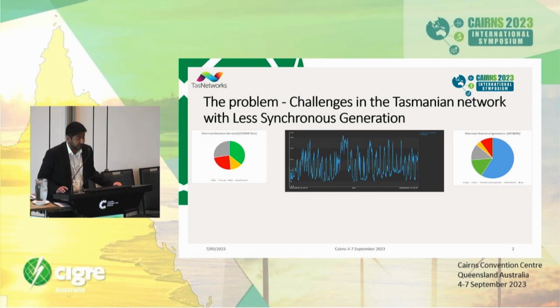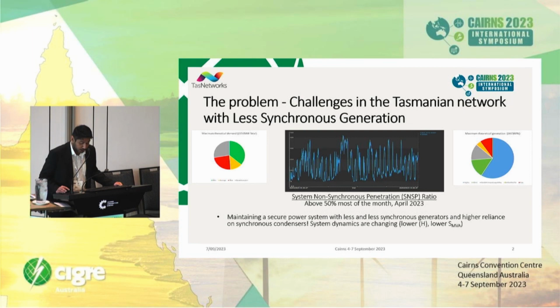So this makes the importance of PMUs clear. We have been using data from PMUs to analyze how much non-synchronous penetration there is in our network, and then we use synchronous condensers to introduce inertia. Apart from that, we have been utilizing PMUs for monitoring the compliance of generating systems, and also to monitor our wind farms' fault ride-through behaviors.